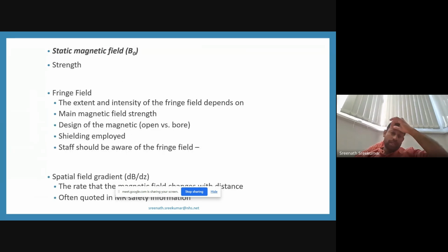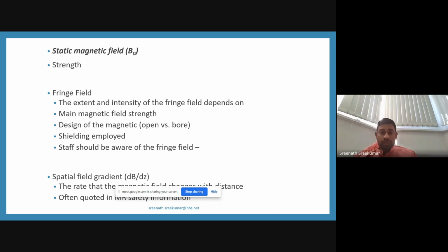So which depends upon the fringe field, and the extent and intensity of the fringe field depends upon the main magnetic field strength, and whether it is an open or closed bore, and both are different, like 1.5 Tesla and 3 Tesla have different field strengths, and that will be different in fringe field strength also. And the shielding will also be different, and that shielding defines how much the fringe field is, and also how much risk will be associated with the machine.